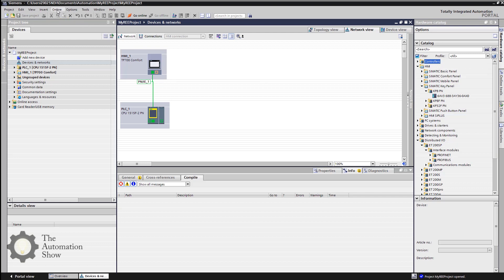We've got green status — everything seems to be good with our PLC configuration. I'll confirm some diagnostics between the PLC and the HMI and activate the PLC's control panel. That gives the drive permission to allow the PLC to control it through the software commissioning wizard. We enable the drive, then activate the forward command, and you can see the current value reply back from the drive for the current set point.